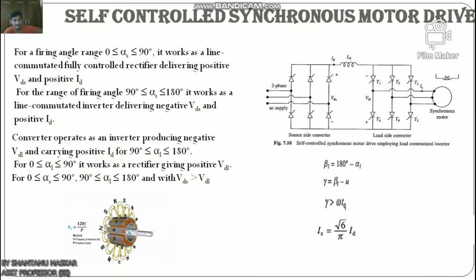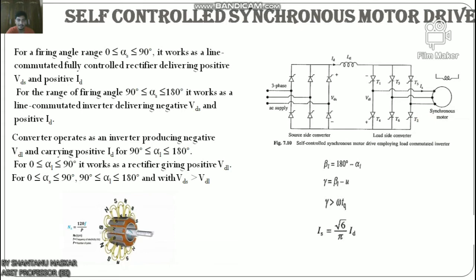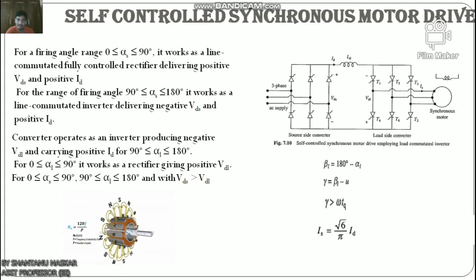For αl in range 0° to 90°, it works as a rectifier giving positive Vdl. For αs in range 0° to 90° and α1 in range 90° to 180°, with Vds greater than Vdl, the source-side converter works as a rectifier and the load-side converter as an inverter, causing power to flow from the AC source to the motor — giving motoring operation. When firing angles are changed such that αs is in range 90° to 180° and α1 is in range 0° to 90°, the load-side converter operates as a rectifier and the source-side converter as an inverter, reversing power flow for regenerative braking.